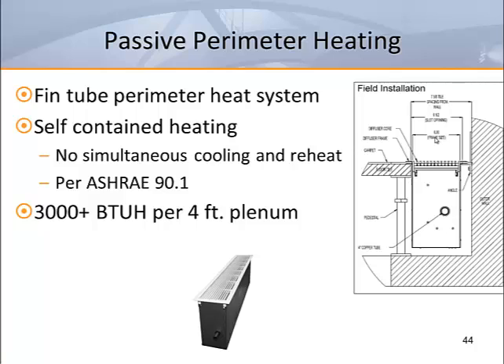For perimeter heating, the fin tube hot water or fin tube electric units are specified. The electric heat unit is controlled by an SCR controller. These plenums are 4 feet in length and 6 inches wide as a standard. They install in the same fashion as the VAV cooling unit previously discussed, with an angle iron on the exterior wall and carpet tile on the room side. This will allow a modular installation to match your climate requirements. How does this passive heating unit work?